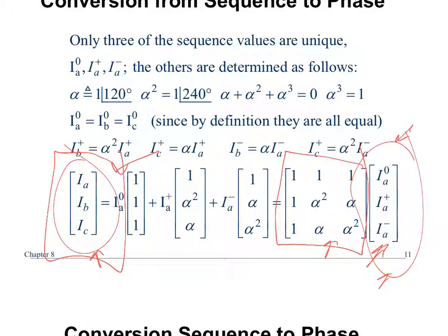Okay? So when you do your initial setup, you need to be able to calculate what the phase currents are going to be. So you can design your breakers or your system to handle those fault currents, but it's all going to be based on coming up with a way to calculate your symmetrical components. Okay? Make sense?